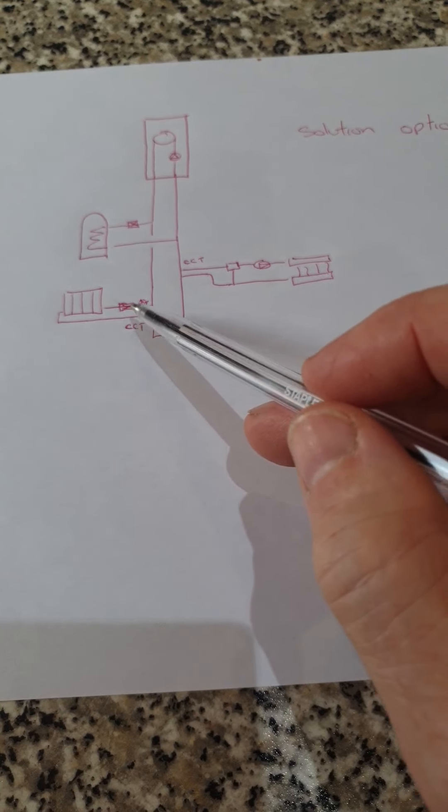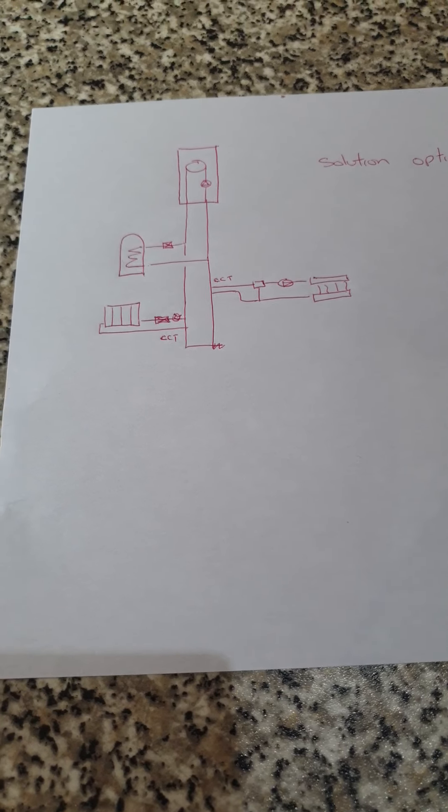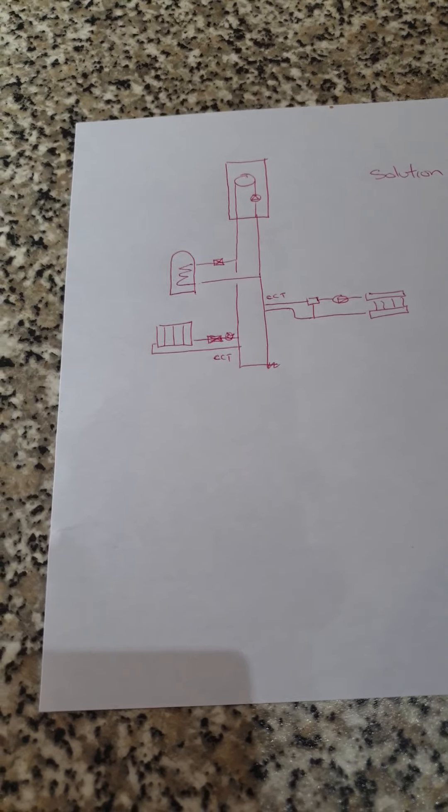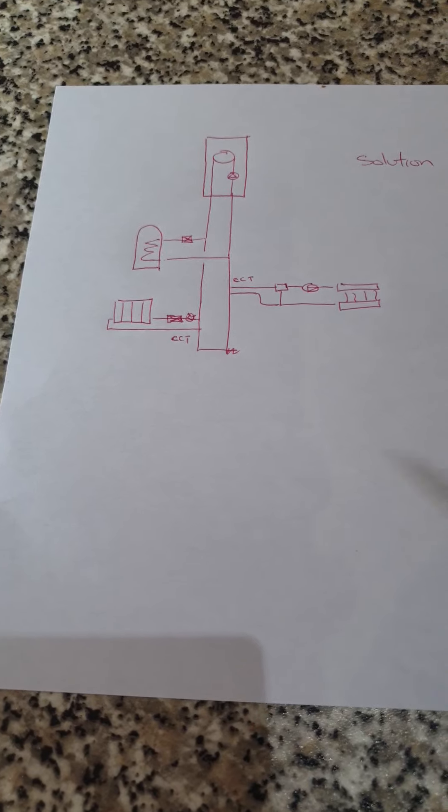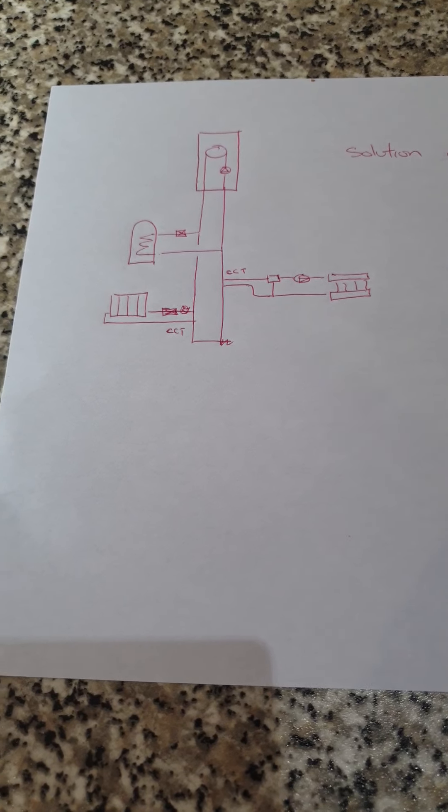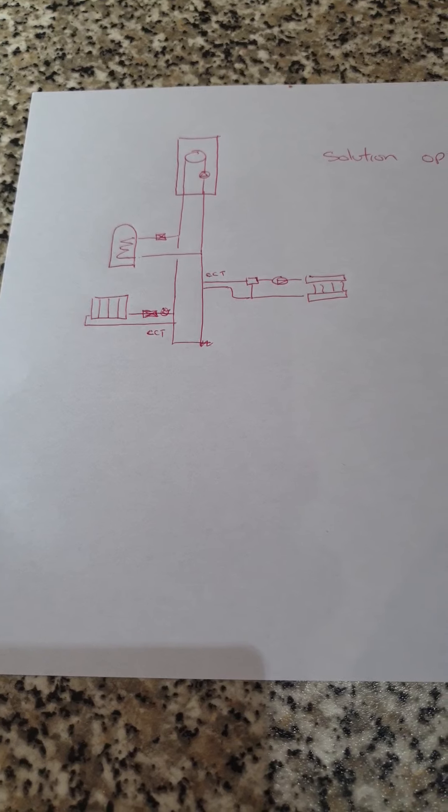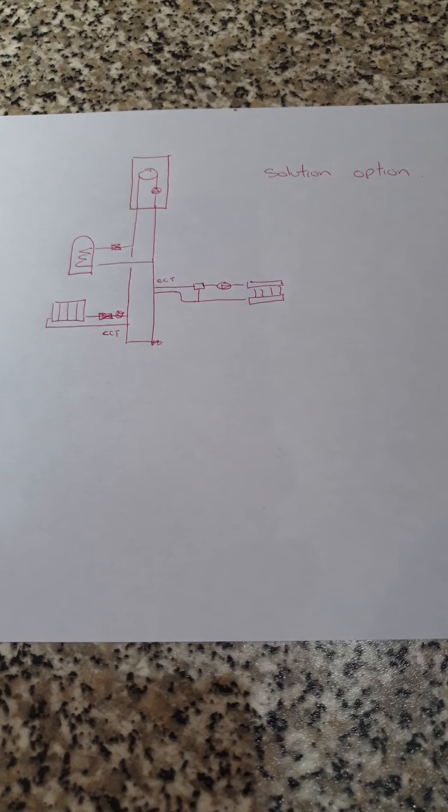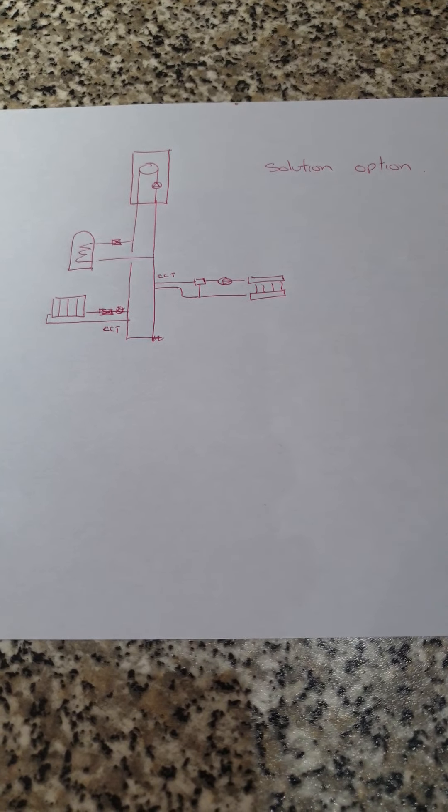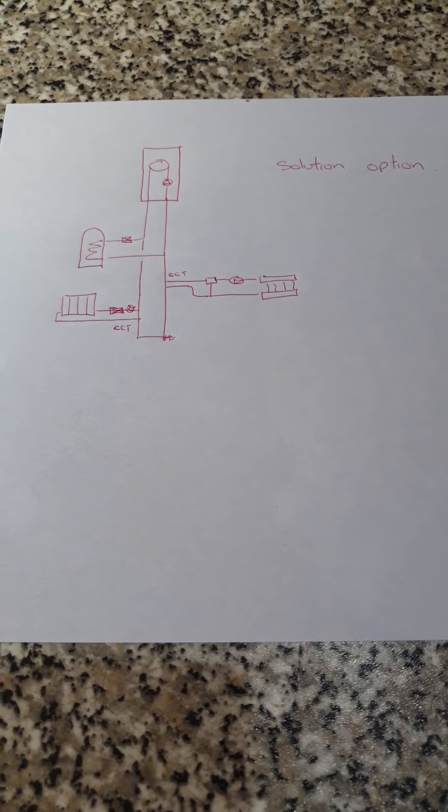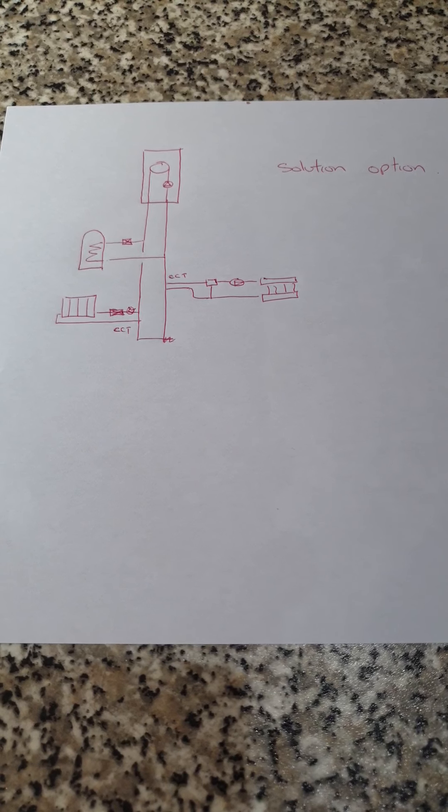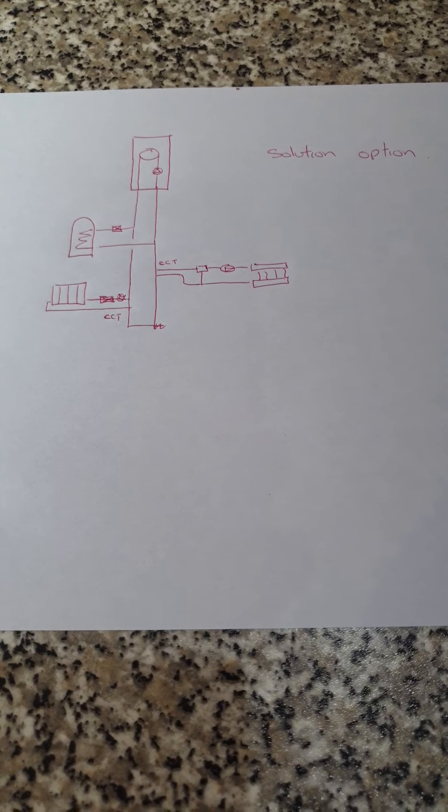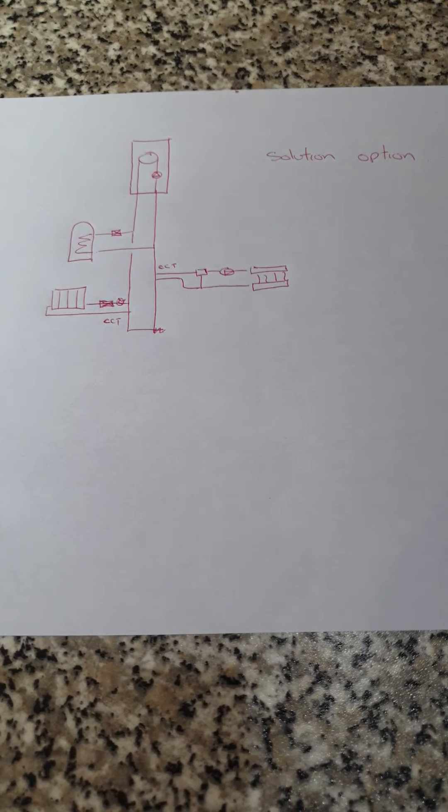And we've got a pump for our radiator circuit into a set of close coupled T's. So, very easy. Just an addition of one pump to the radiator circuit. And instead of coming back on the return side, coming in as a close coupled T. And that I think would be able to be applied to a lot of situations. But you've got a few options there. So, but no close coupled T's just on underfloor manifolds. It's a very, very big mistake in my book. Thank you.